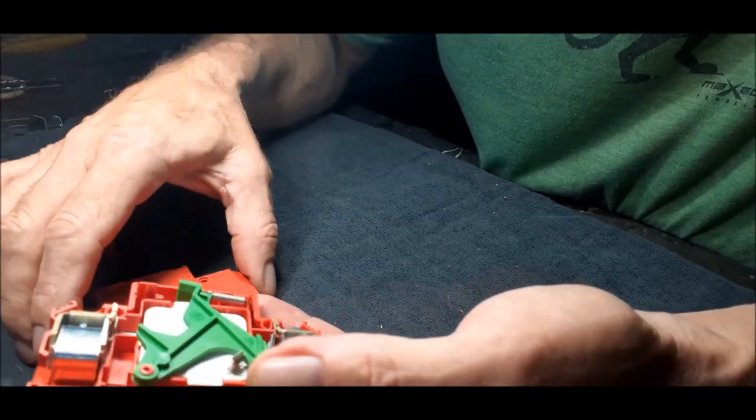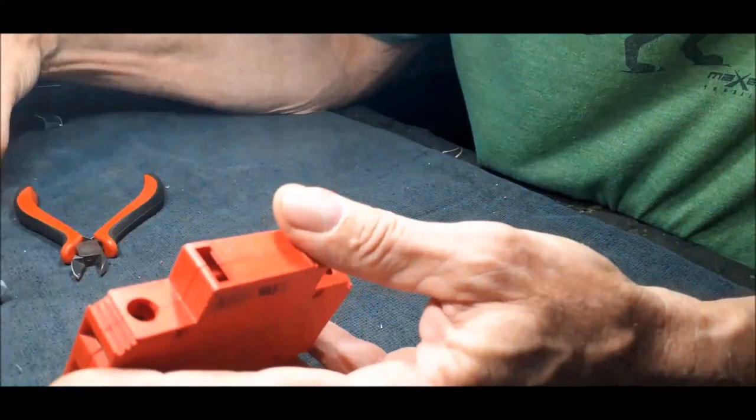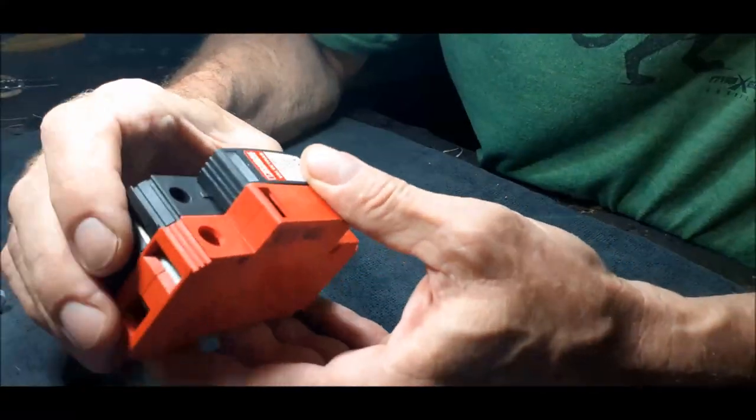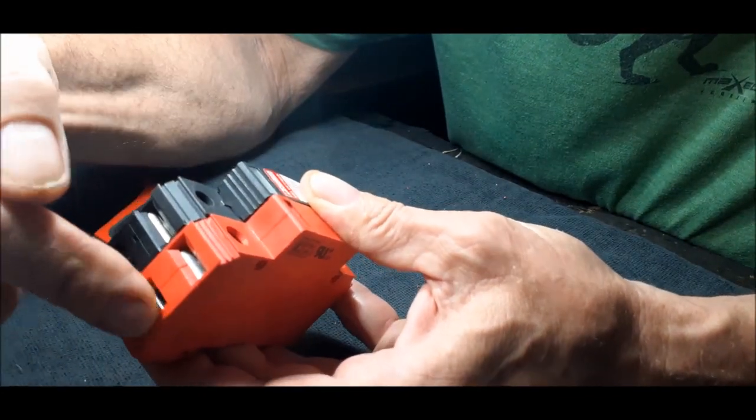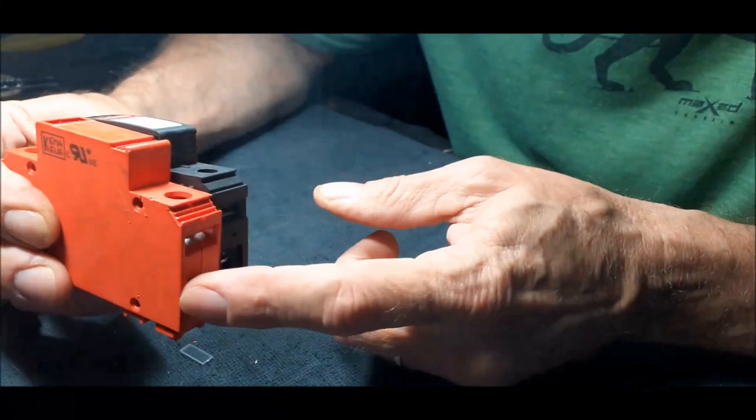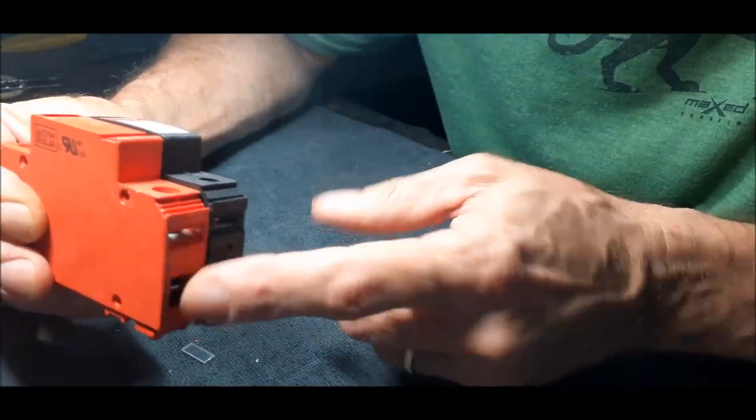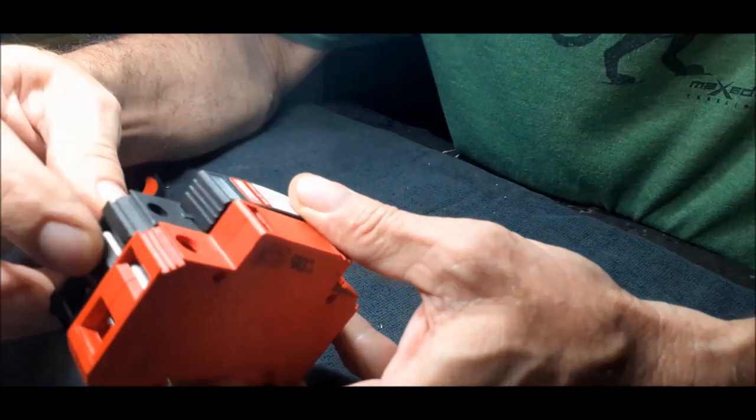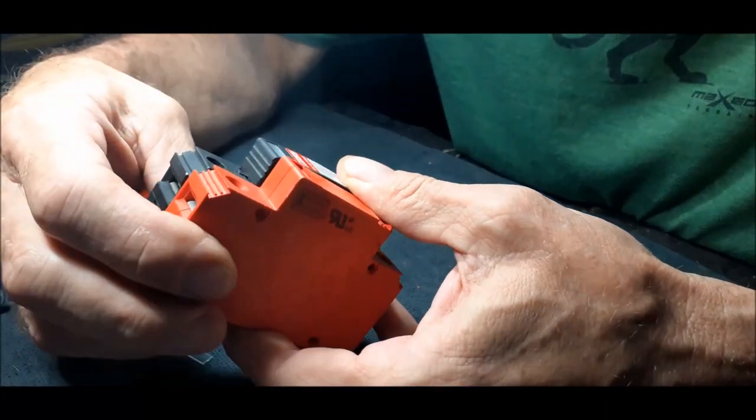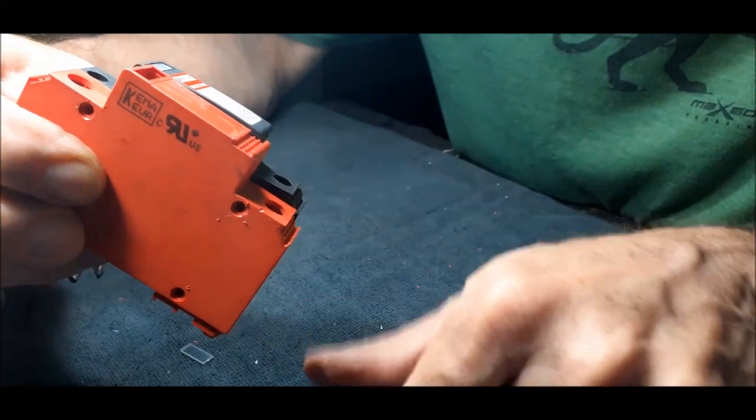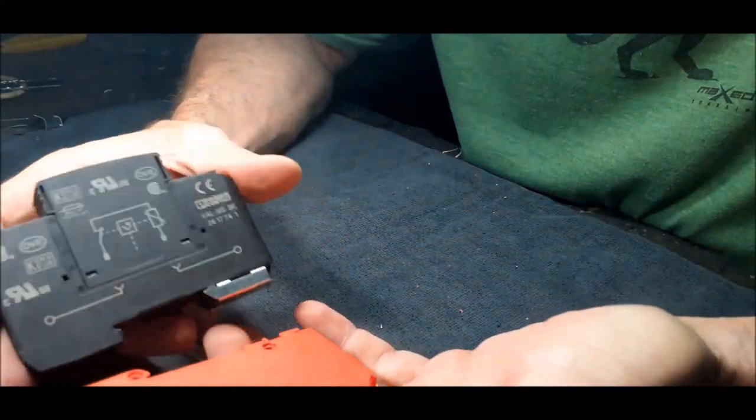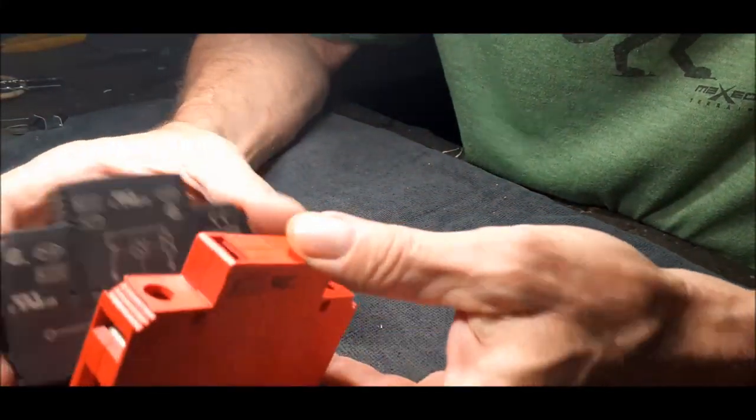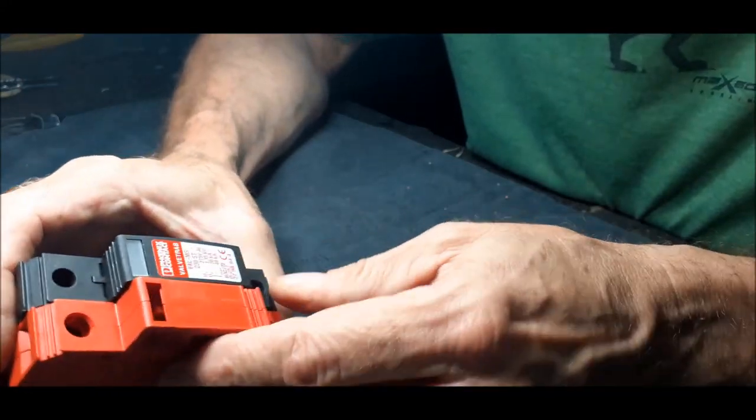How you connect this thing, you normally get two next to each other. Then you connect your live from your live input here, and from your neutral input there. And in the back, you connect them both together to your ground. So any spike that comes down the line between live and neutral, it will divert the spike back to ground. This is where you normally use it. You get different ways of connecting it also, but it's the basic way.